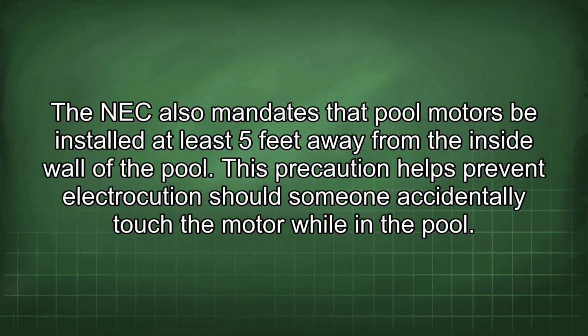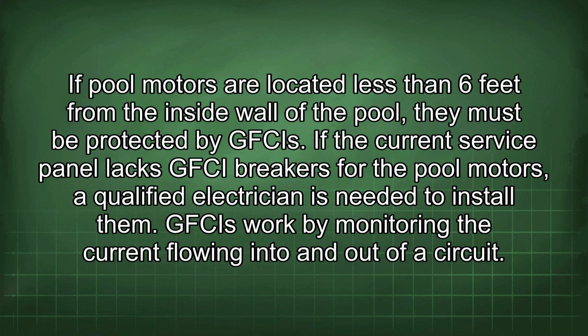The NEC also mandates that pool motors be installed at least 5 feet away from the inside wall of the pool. This precaution helps prevent electrocution should someone accidentally touch the motor while in the pool. If pool motors are located less than 6 feet from the inside wall of the pool, they must be protected by GFCIs.